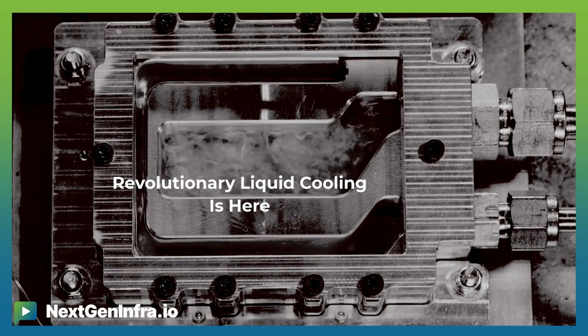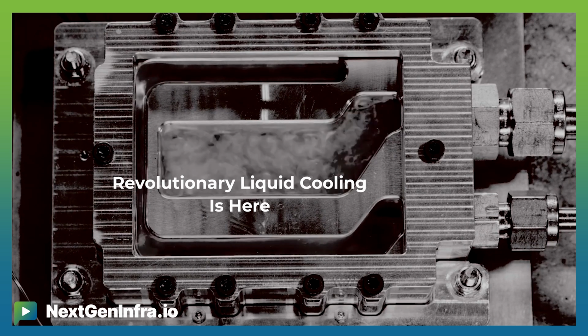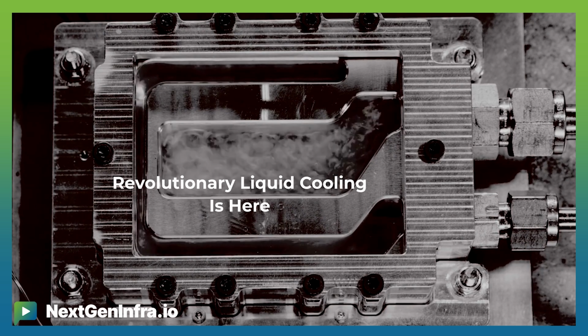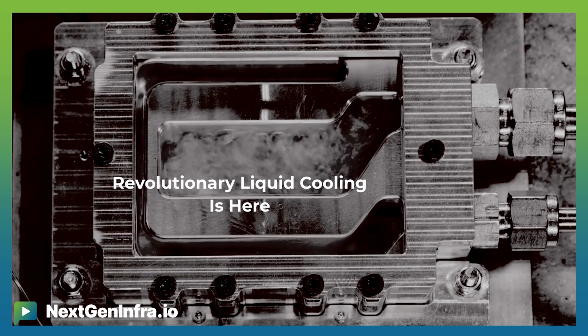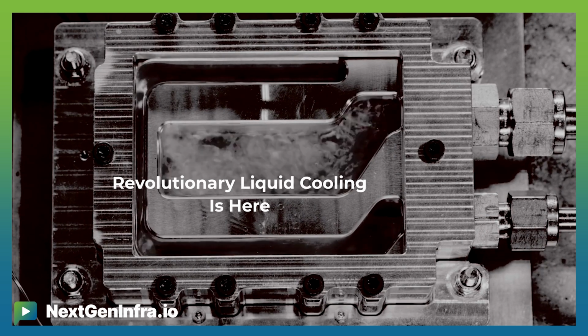Traditionally, with direct-to-chip liquid cooling, they're bringing water-based mixtures over a chip. That water comes across, simply removes the heat, and takes it away in a single-phase mode — it's just straight up liquid cooling. With two-phase cooling, we bring a fluid that's near its saturation point, and as soon as it hits the chip, the heat causes the fluid to boil. That vigorous boiling process provides a natural mixing that ultimately takes heat off the wall much more efficiently than the single-phase mode.